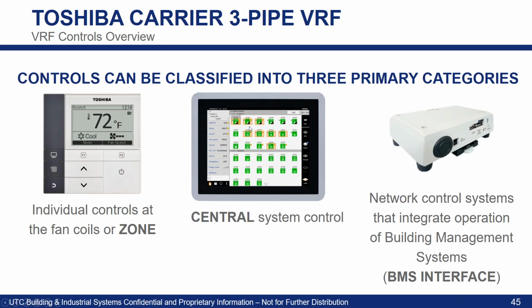We like to recommend these because this would be our central controller for, let's say, if you didn't have a building automation system within your building. You would definitely want a central system control so you can see everything that's going on with your VRF systems all in one location. These also have remote viewing app availability. So really, if you've got an IP connection, you can do remote control with this color touch screen. To the right here, if you do have a BACnet system or an automation system, we do have a BMS interface.